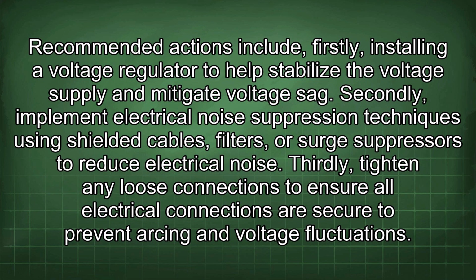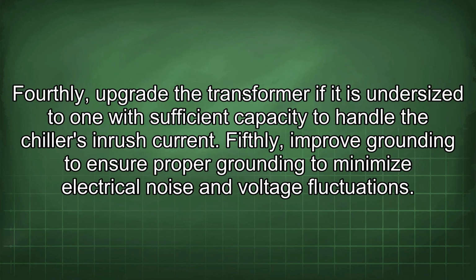Recommended actions include: firstly, installing a voltage regulator to help stabilize the voltage supply and mitigate voltage sag. Secondly, implement electrical noise suppression techniques using shielded cables, filters, or surge suppressors to reduce electrical noise. Thirdly, tighten any loose connections to ensure all electrical connections are secured to prevent arcing and voltage fluctuations. Fourthly, upgrade the transformer if it is undersized to one with sufficient capacity to handle the chiller's inrush current. Fifthly, improve grounding to ensure proper grounding to minimize electrical noise and voltage fluctuations.